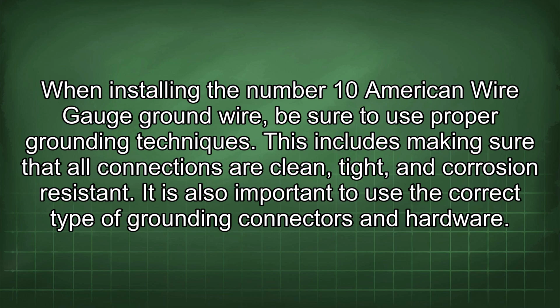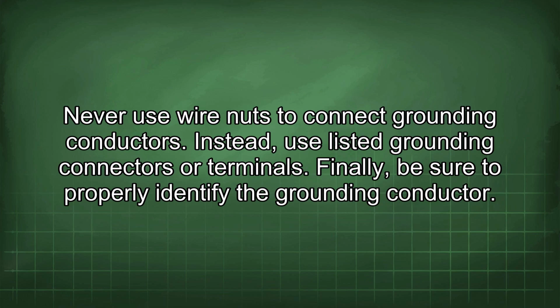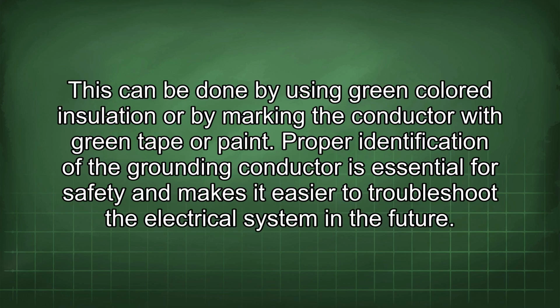When installing the number 10 American wire gauge ground wire, be sure to use proper grounding techniques. This includes making sure that all connections are clean, tight, and corrosion resistant. It is also important to use the correct type of grounding connectors and hardware. Never use wire nuts to connect grounding conductors. Instead, use listed grounding connectors or terminals. Finally, be sure to properly identify the grounding conductor. This can be done by using green-colored insulation or by marking the conductor with green tape or paint. Proper identification of the grounding conductor is essential for safety and makes it easier to troubleshoot the electrical system in the future.